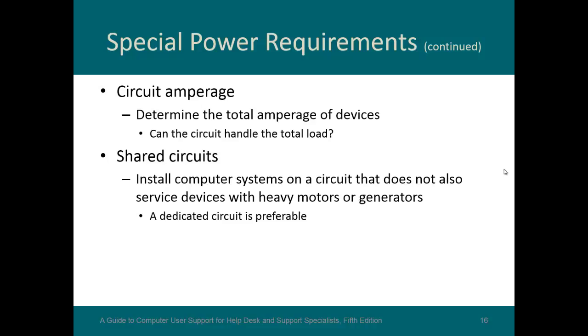Shared circuits: make sure your computer systems aren't on the same circuits as motors and generators. We had an issue once where someone ran data lines and wrapped one around the motor of an elevator—so every time the elevator ran, it interrupted the data signal. Sometimes when motors and generators start up, they draw a lot of power and can cause everything else on the same circuit to shut down. Make sure you're aware of that.